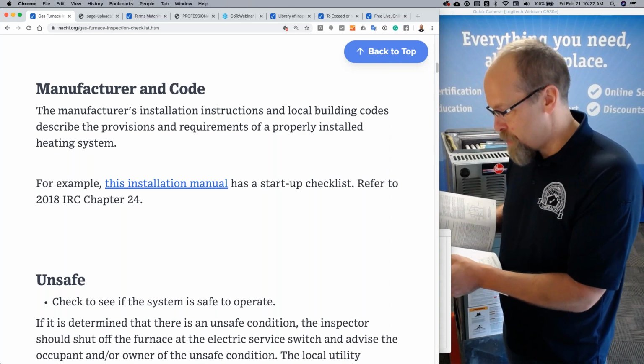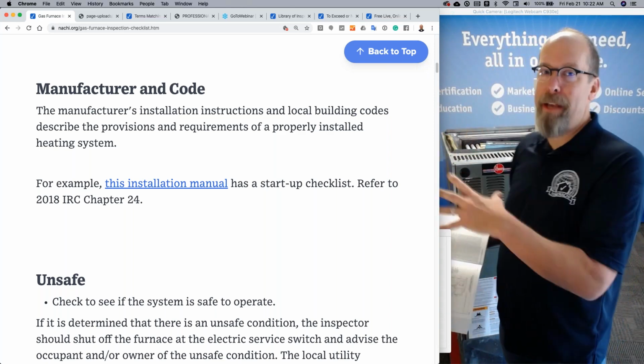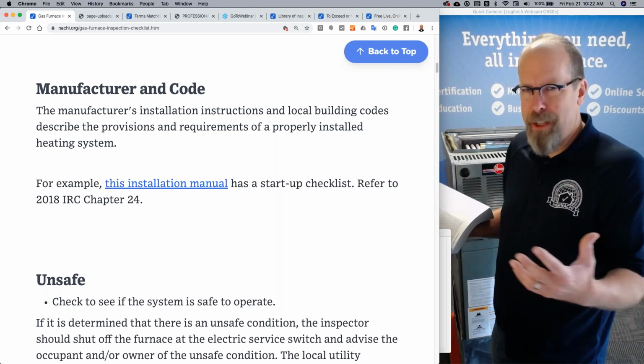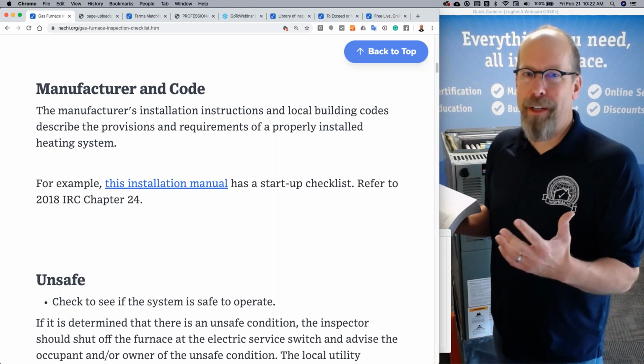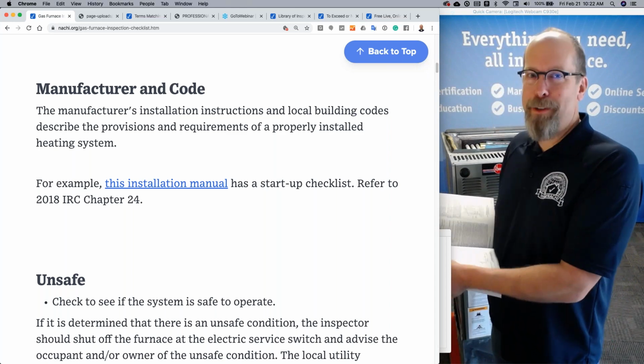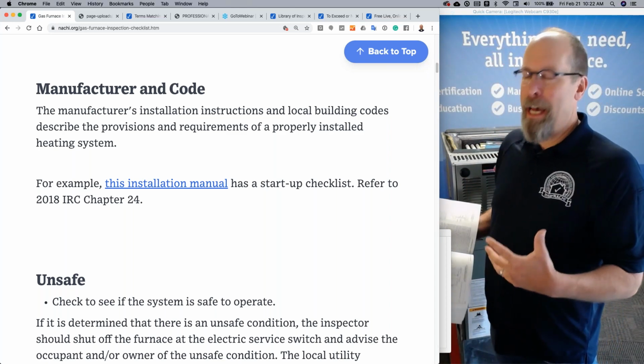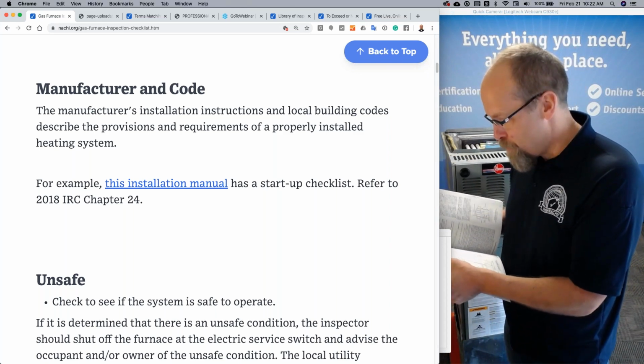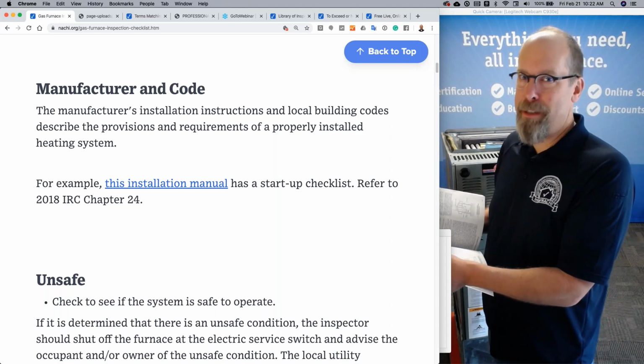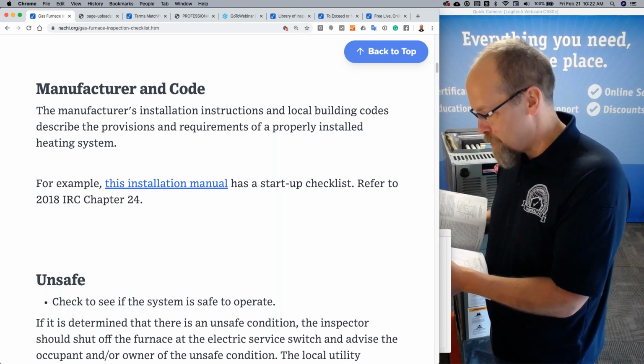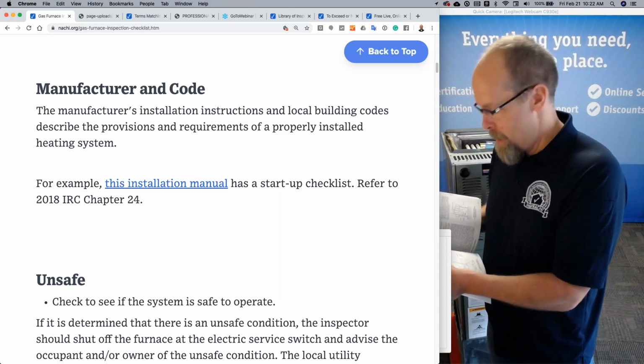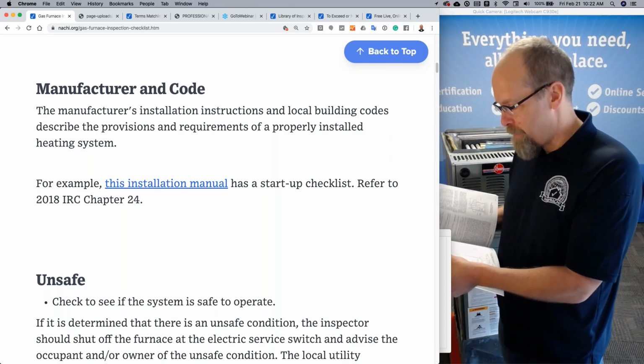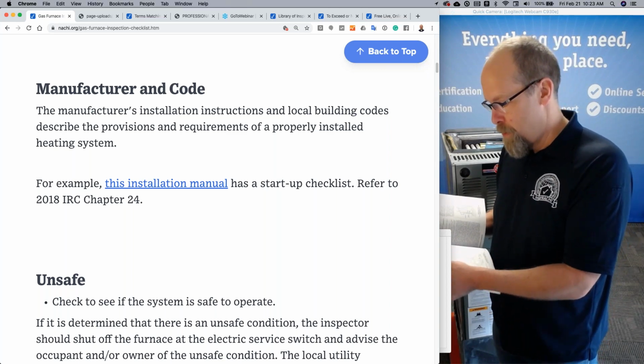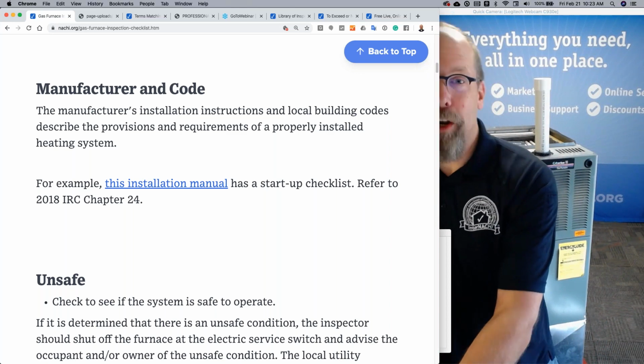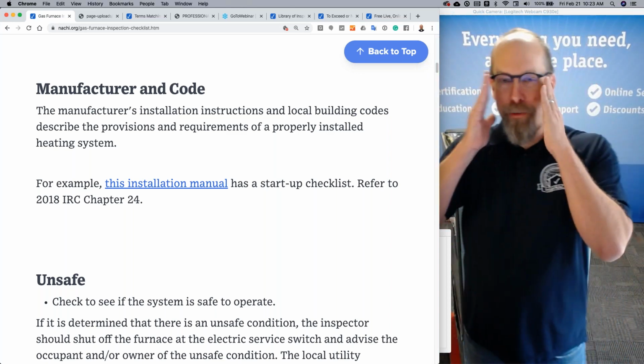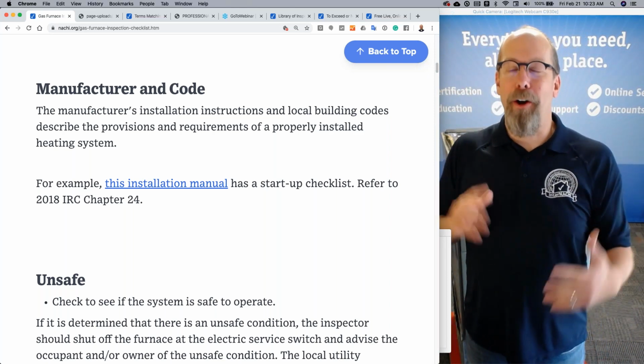The required room volume is determined by two methods. If you have a furnace down in the basement or in a utility room, and it feels kind of small, usually they are. Sometimes they feel like they're in an unfinished closet, right? It's really small. I don't know why they install them in it. It's such an important piece, it's the lungs of the house, and yet they put it in a really small room. But the required room volume, how big the room should be in which the heating system is installed, is determined by two methods. One method is based upon the actual air infiltration rate of the building, and that's where you need something like a blower door. The other is based upon the familiar fixed ratio of 50 cubic feet per 1,000 BTU per hour. Those are the two methods, and we don't go there at all to determine room volume in relation to the heating system and the BTU. Thank goodness, we'd be there all day doing that, right?